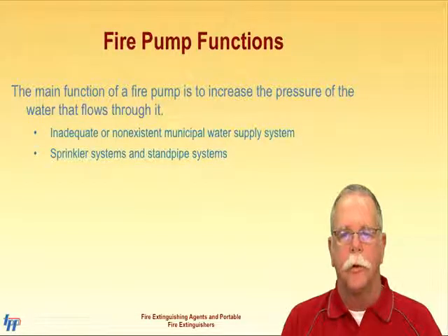Fire pumps as described are used to increase water flow and pressure for fire suppression. As an example, a high-rise building that is sprinklered would not have enough pressure from the municipal water system to reach the upper floors with adequate pressure to effectively operate sprinkler heads. Therefore, a pump may be added to the system to augment that pressure.